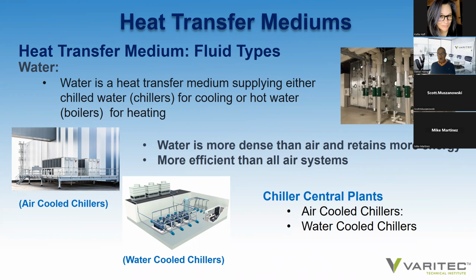Chiller central plants are common for, well, are required for chilled water systems. There are air-cooled chiller solutions and there are water-cooled chiller solutions. And both vary depending on how we evacuate the building energy into the ambient condition. An air-cooled chiller will evacuate that energy into the ambient air through the condensing section of the chiller, or in a water-cooled central plant, a chiller will evacuate that building energy to a cooling tower loop that uses evaporation in the cooling towers to finally eject the energy absorbed from a building.